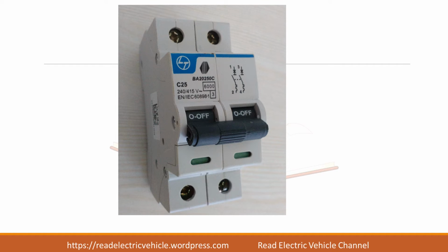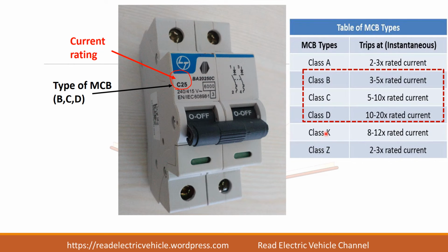Next we will see the nameplate details. So first you have C25 written here. What is this C25? C stands for the type of MCB. So we know there are different types of MCB. Though there are different types, B, C, D is the widely used one, and B type means it will trip at 3 to 5 times the rated current, and C type will trip at 5 to 10 times the rated current, and D type will trip at 10 to 20 times the rated current. So B and C are mostly used for residential purposes, and D is used for industrial purposes, or for high inrush current machines like X-ray or large motors, you can use class D.